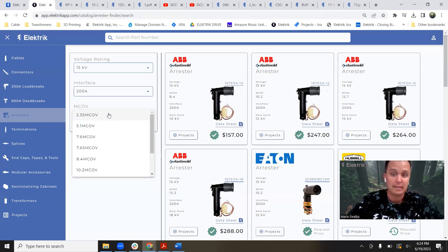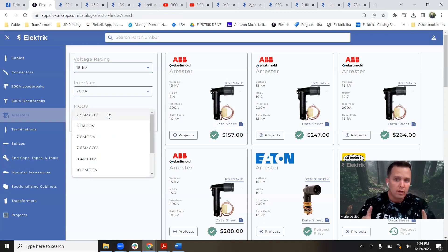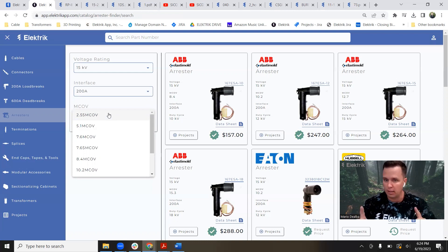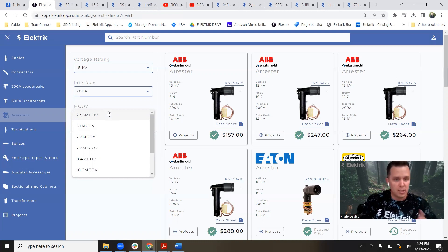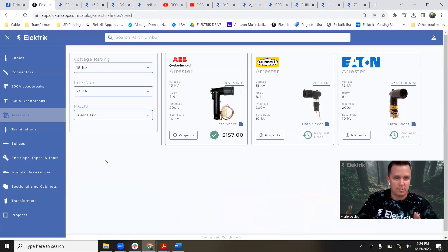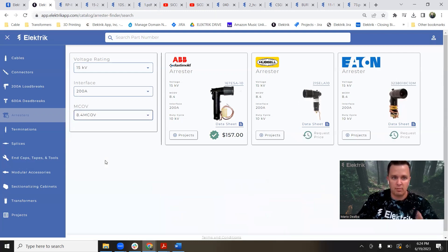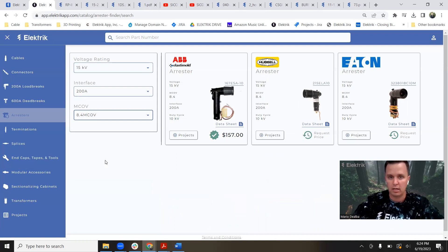After you choose the interface, the MCOV is very important. Don't confuse the MCOV with duty cycle — those are two different things, although they're correlated. A very common arrestor is going to be the 8.4 MCOV, which is your everyday 15 kV circuit type of arrestor.